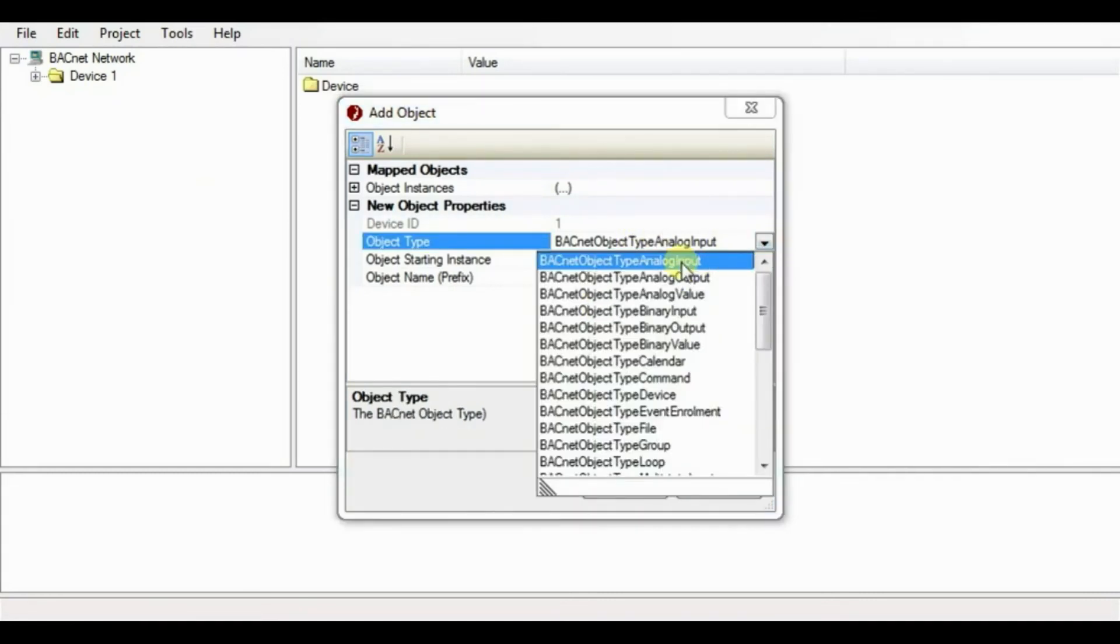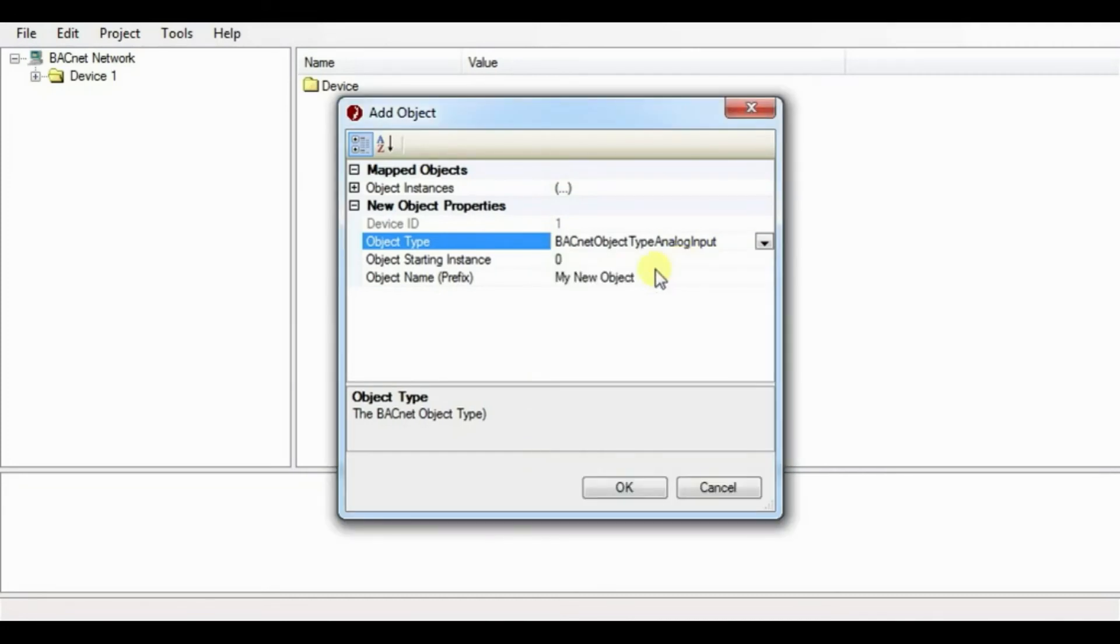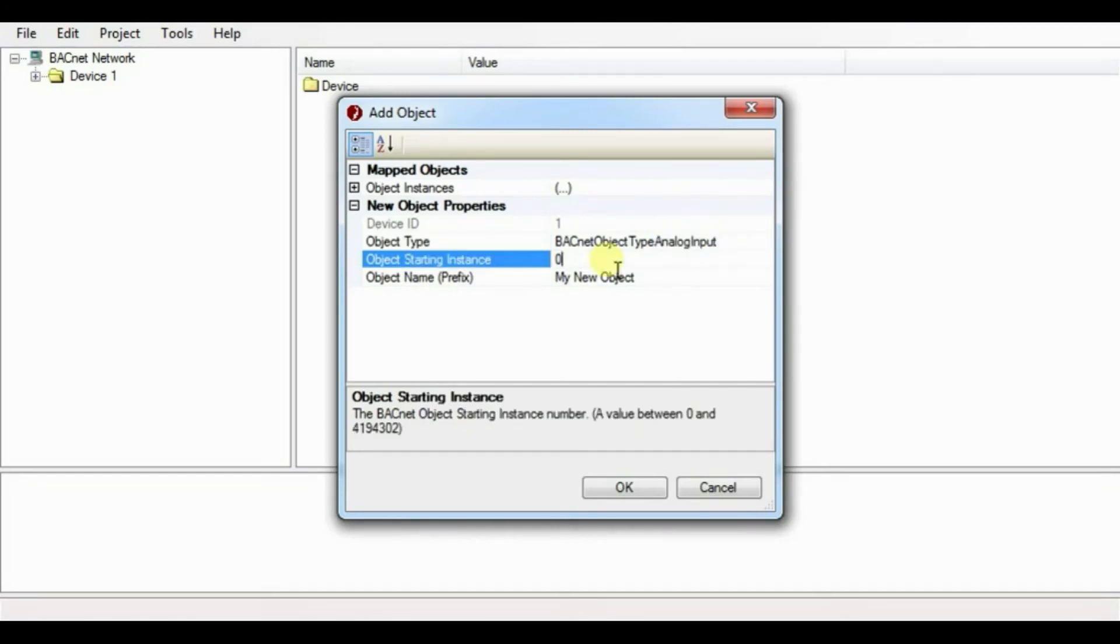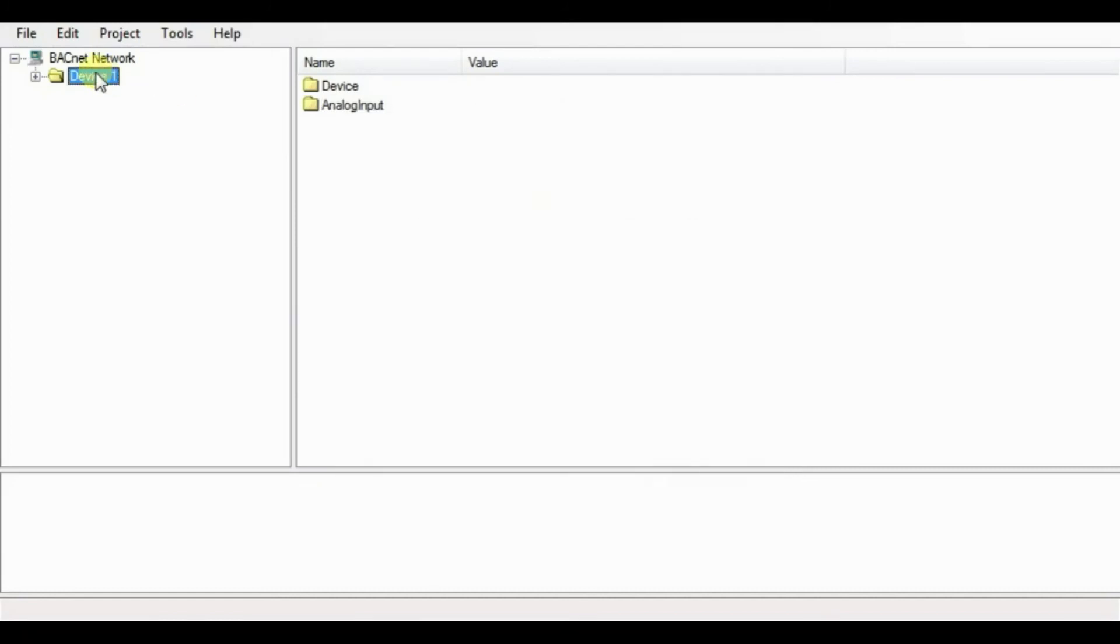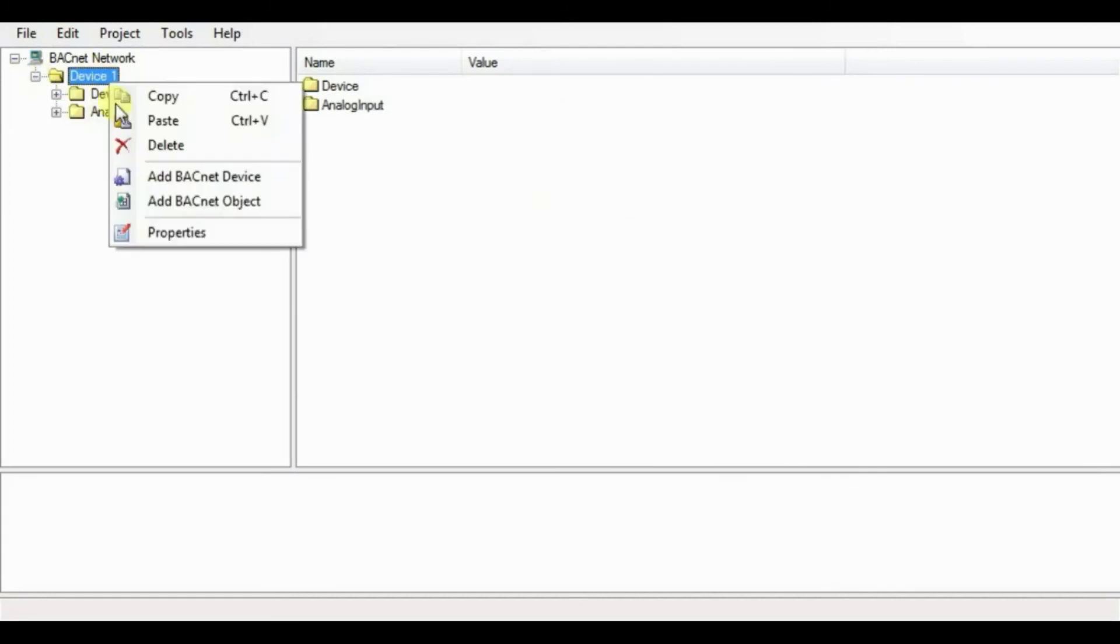In our case, we will perform the read properties. So we will use BACnet object type as analog input followed by its instance number and its name. Same way we will add the object for binary input.